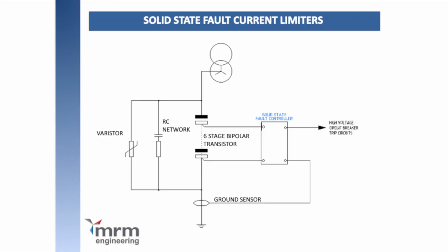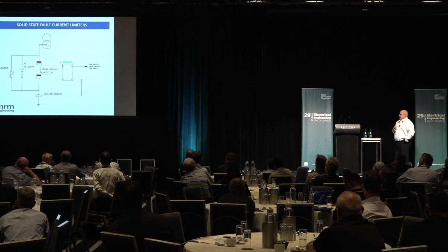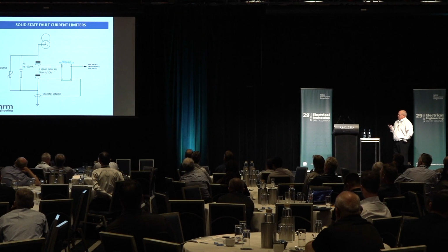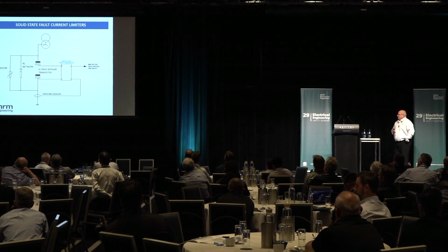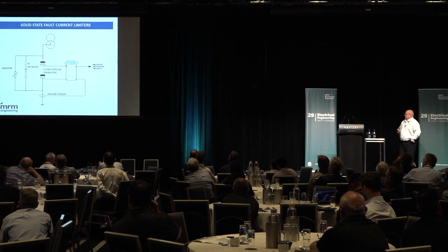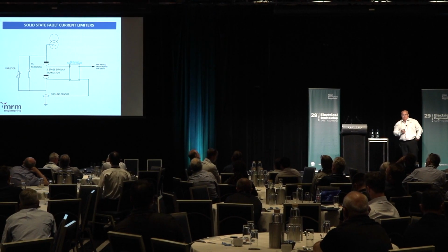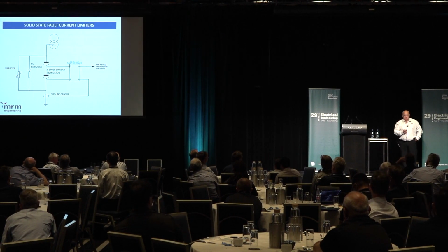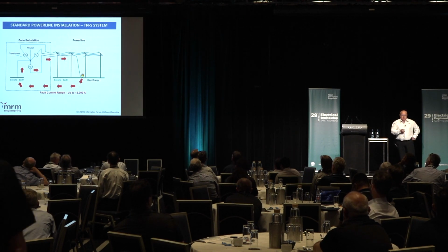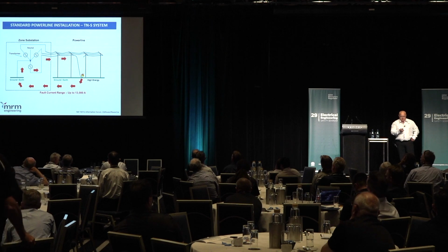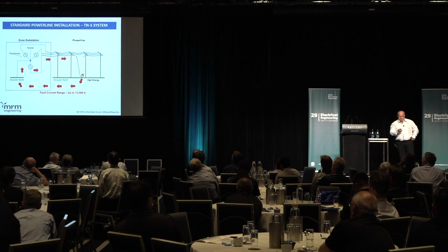So up on the diagram, again, the NER has been replaced with a series of IGBTs with a controller, and then you've got your capacitive network around that and your over voltage protection. So it basically looks like hooking in an inverter controller for your neutral connection. So this is just a diagram for your standard TN-S system, which is the MEN, which is used in distribution networks. So follow the red arrow.